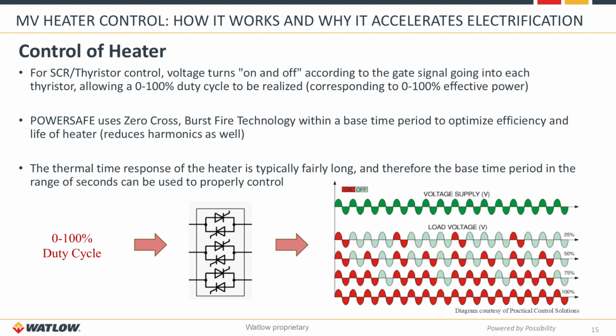So let's dive into that just a little bit deeper. There are a couple different types of control that you can do with a heating element. You can do what's called contactor control. That's basically on and off technology. If the contactor is on, you're getting 100% duty cycle out to that heater. So 100% of your voltage gets applied to the heater and 100% power is on. You can't really change that. It's either all on or it's all off with a contactor.